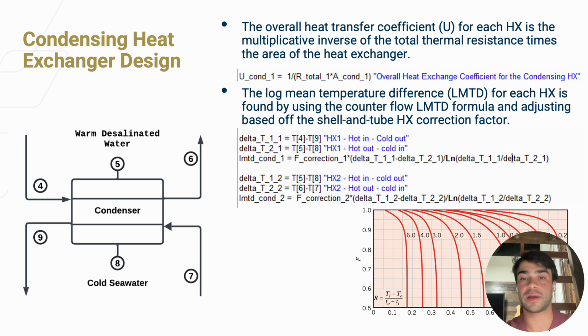The LMTD method is used by finding the counterflow LMTD formula and adjusting this based off of the shell and tube heat exchanger correction factor for a two-pass heat exchanger. We find our correction factor on the chart below, and for the condensing heat exchanger, it will be 1. However, for the subcooling heat exchanger, it will be somewhere between 0.9 and 1.